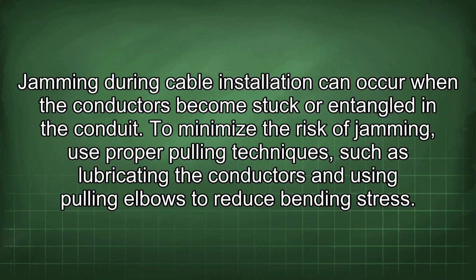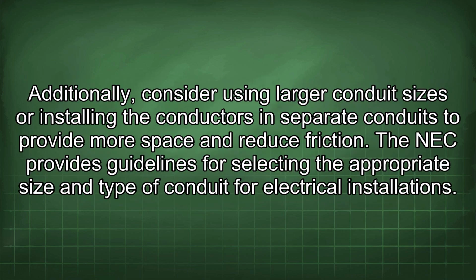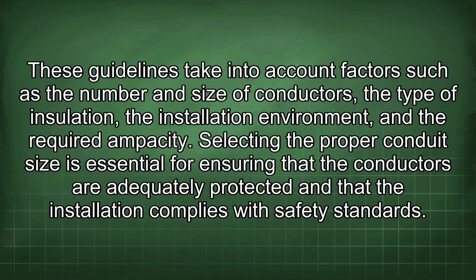To minimize the risk of jamming, use proper pulling techniques such as lubricating the conductors and using pulling elbows to reduce bending stress. Additionally, consider using larger conduit sizes or installing the conductors in separate conduits to provide more space and reduce friction. The NEC provides guidelines for selecting the appropriate size and type of conduit for electrical installations. These guidelines take into account factors such as the number and size of conductors, the type of insulation, the installation environment, and the required ampacity.